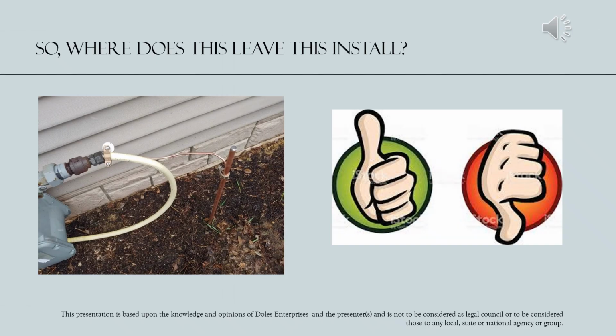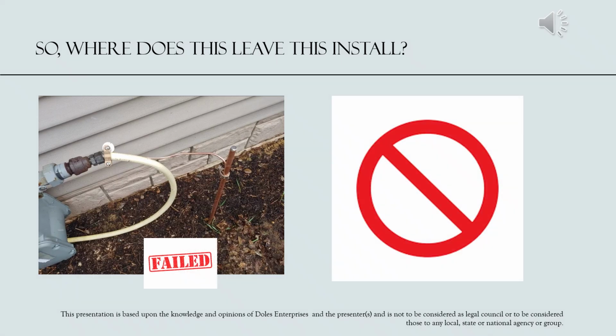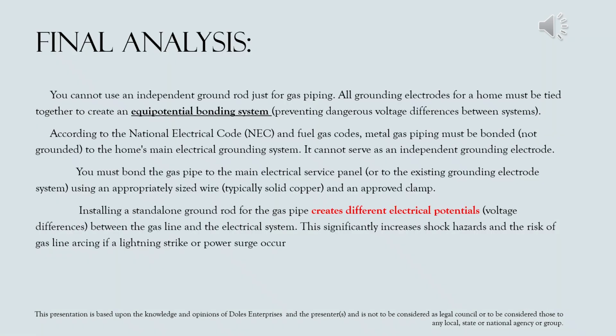So where does this leave us as far as the example that we started off with? This, of course, is a thumbs down as far as I'm concerned. If I were looking at this installation, I would put a fail and then ask for whoever did this to give me a call. I'd love to talk to them. You cannot use an independent ground rod just for the gas piping. You just can't do it.